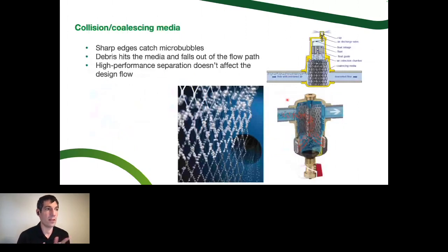Okay, so I mentioned this before. The coalescing media is a very fancy way of saying to gather. So a coalescing media, there are different manufacturers that are going to make different versions of this same kind of device, where you're going to have some sort of media with sharp edges where we're going to have a little eddy with the flow of the water coming through, that it's going to get kind of hung up on a little knife edge. In our case, it looks a little bit like a honeycomb, that it gets right into an eddy on that sharp edge, and then it gathers into bigger bubbles as more bubbles get hung up on that same edge, and then as they get bigger, they float up to the top, which is the same air vent that was described before. So coalescing media is helpful to get those little micro bubbles out.